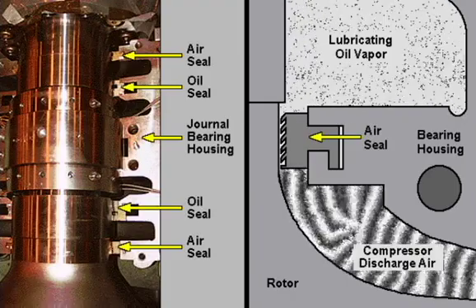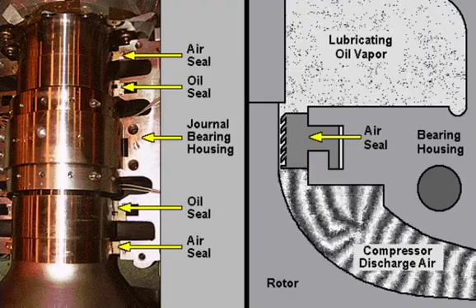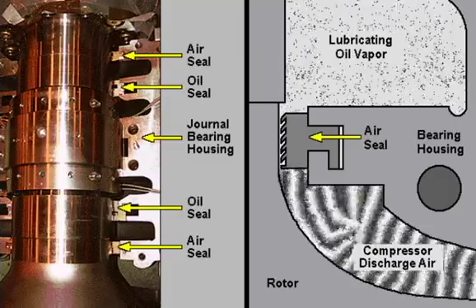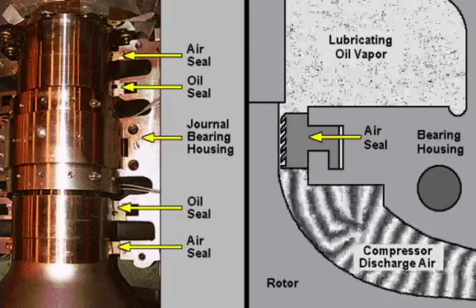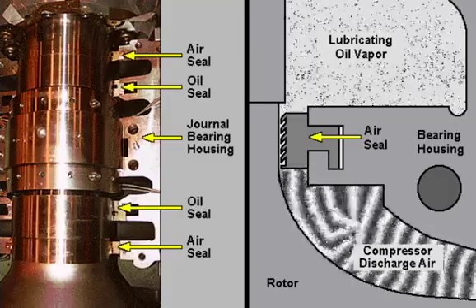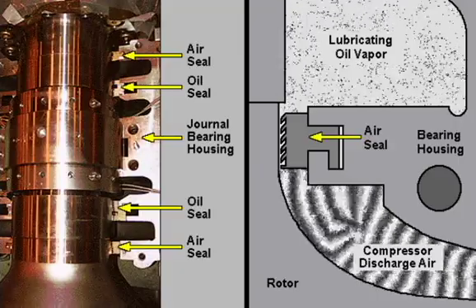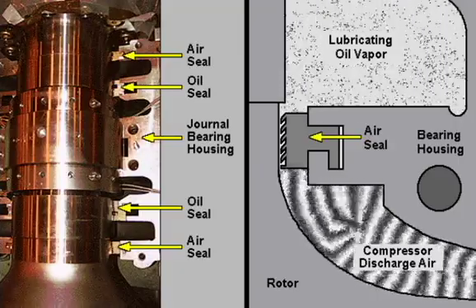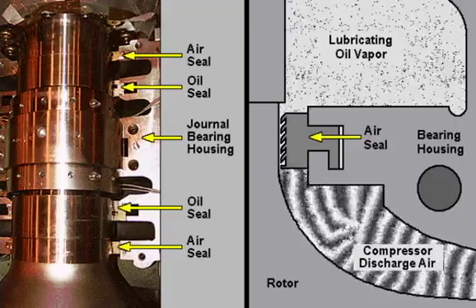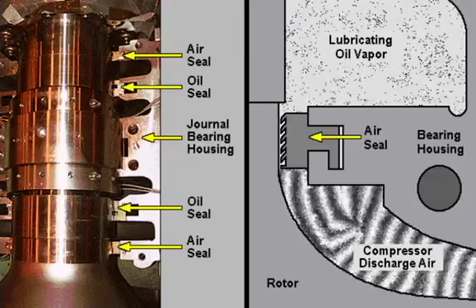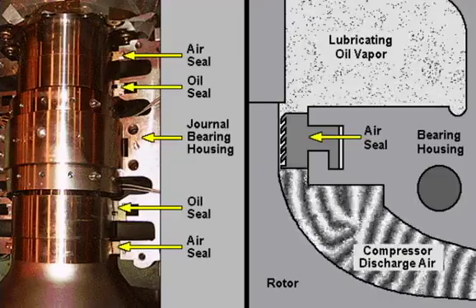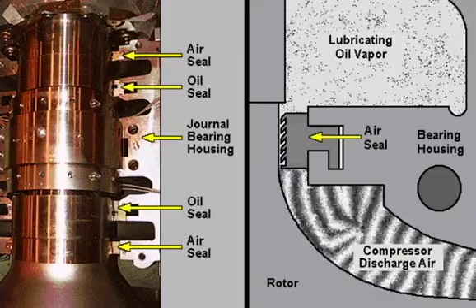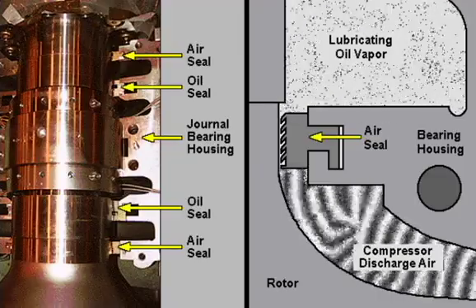The air seals the bearings by containing within the bearing housing any lubricating fluid that leaks past the oil deflectors. Air is directed to both ends of each bearing housing and flows along the journal into the bearing cavity, providing a pressure barrier to the lubricating fluid.